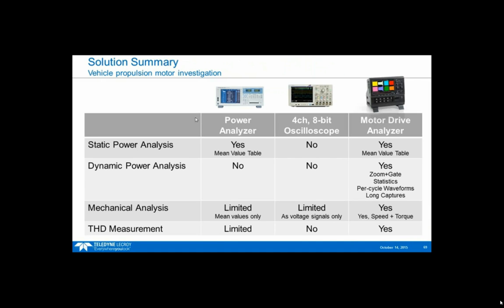So again, solution summary for this vehicle propulsion motor. There are a couple of instruments that do the static analysis, and we showed the dynamic analysis with zoom and gate statistics, waveforms, and a very long capture time. We have the THD measurements, you get a value but not the waveform there; here you get values, waveforms, statistics, and so on. The mechanical analysis here has limited capability, giving you a value for speed, torque, and mechanical power. But here it shows you the speed and torque, plus the waveforms, giving a much richer set of information.